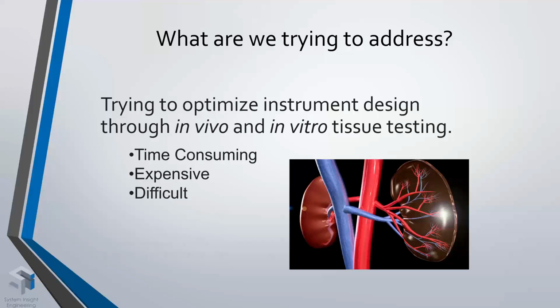And this is a difficulty. But the main reason is that when you start working with biological tissue sources, you suddenly have a very noisy data source. So the ways to overcome that, if you're looking at very subtle differences in the design changes for your device, as in terms of whether A or B is better, it's very difficult to determine if you're using biological tissue as your testing medium, because that's where a lot of that noise is introduced, and just the fact that you've got this variation in tissue between animals, between tissue sources, between time of day, how much hydration there is, and whether it's been sitting out, what the treatment of that tissue's been since harvesting.